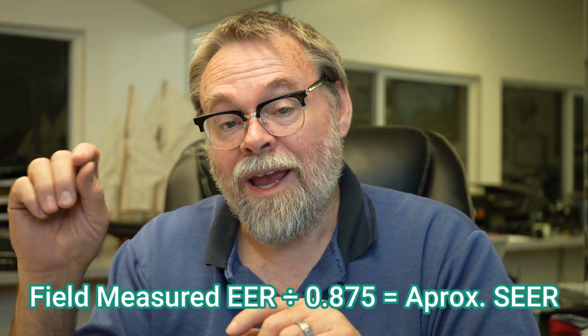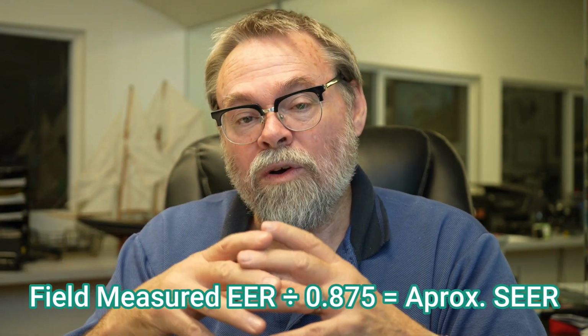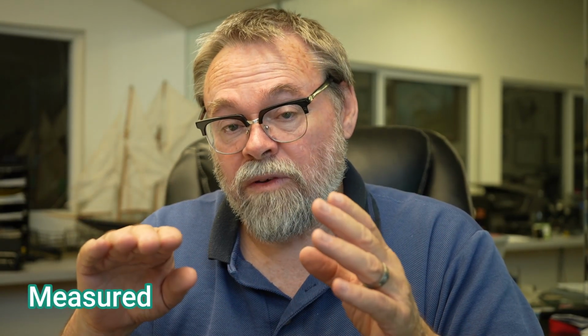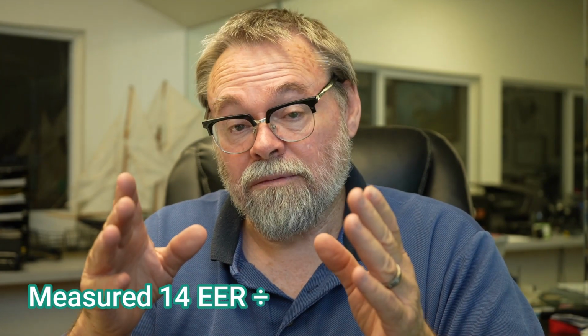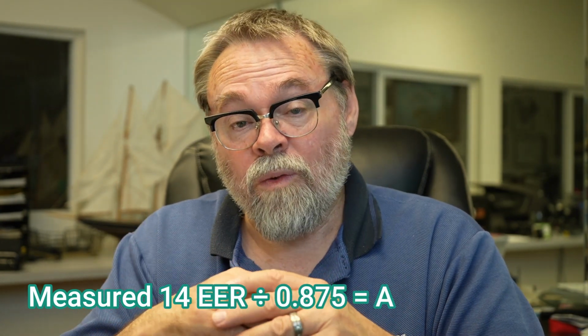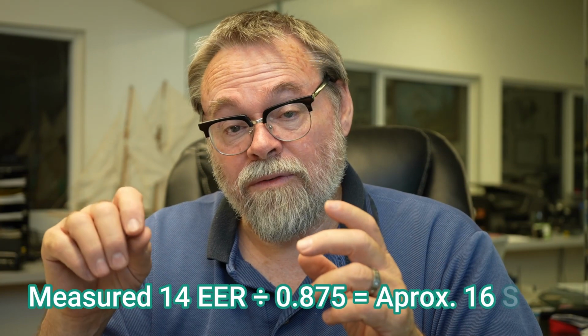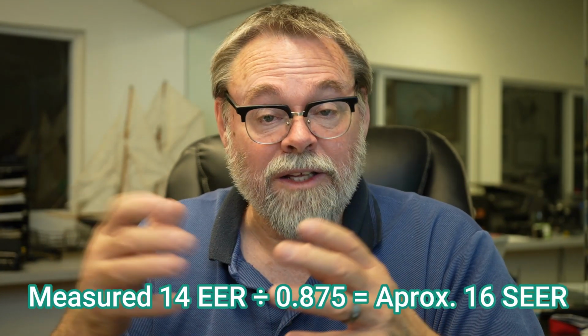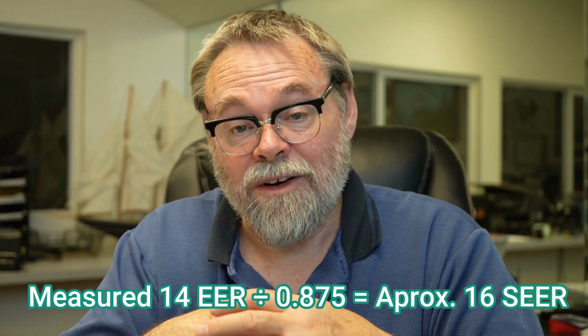Again, I can measure EER in the field. I cannot measure SEER in the field. However, I can take the EER I get and divide it by 0.875, and that will give me the approximate SEER, or very close to it. For example, let's say I measure the EER of a piece of equipment and it's 14. Well, if I divide that by 0.875, it comes out to 16. So the approximate SEER is 16 SEER.